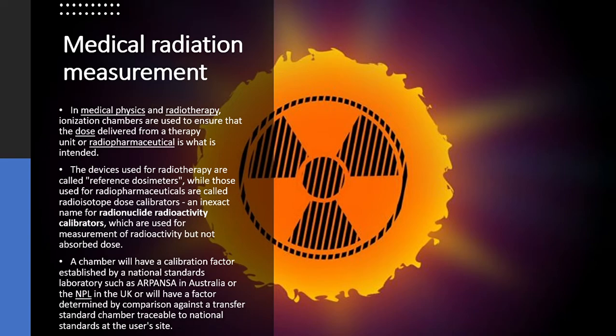A chamber will have a calibration factor established by a national standards laboratory such as ARPANSA in Australia or the NPL in the UK, or will have a factor determined by comparison against a transfer standard chamber traceable to national standards at the user's site.